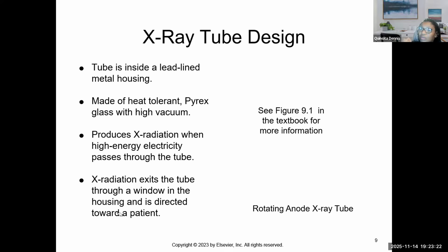It blocks those X-ray photons, what we would call the stray or off focus radiation. We only want the radiation to exit out of the window, which is the part that is facing the patient. Now, all of our tubes do have a certain amount of leakage radiation that they can have by law, but in most cases, everything is exiting from the window.